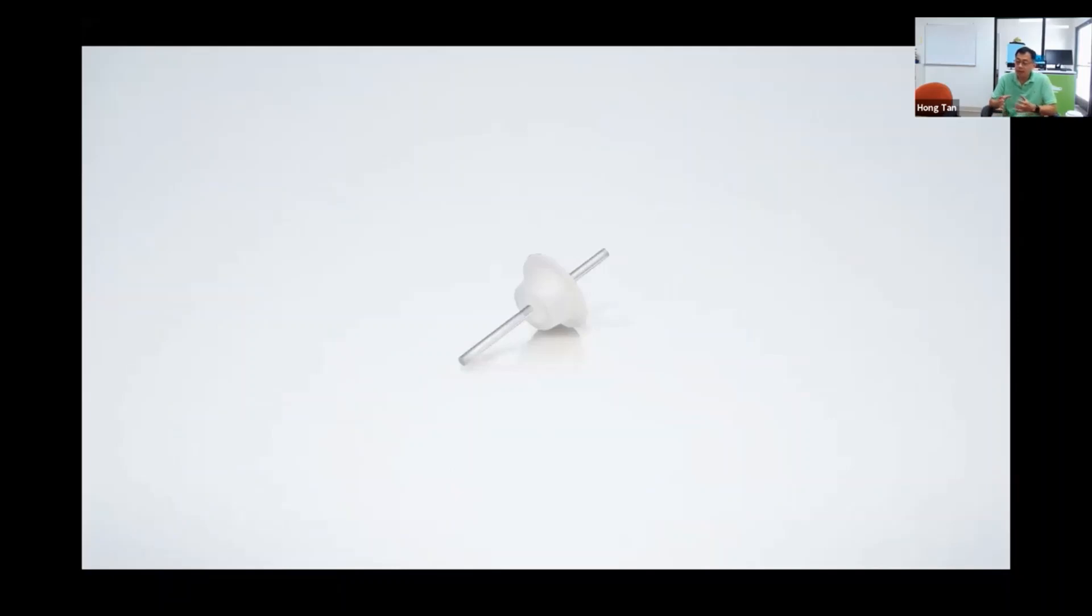BLI is built on this small device. I have it here in my hand, a very small device. We call it the probe. In the center, it is a one millimeter diameter glass rod, 20 millimeters long. We build everything on this.